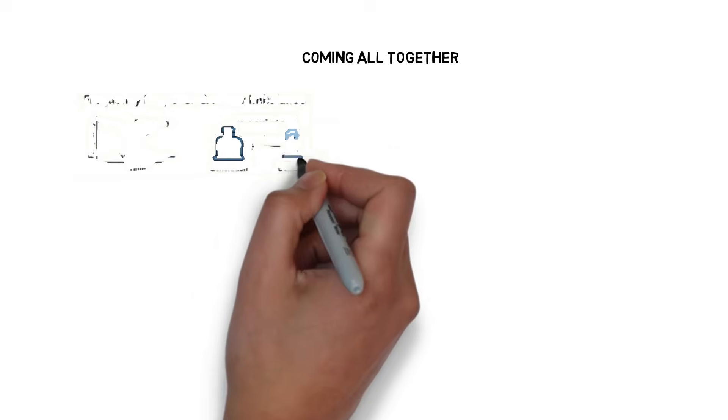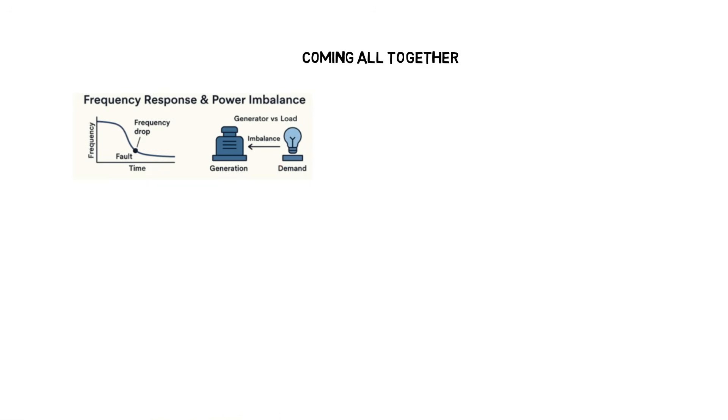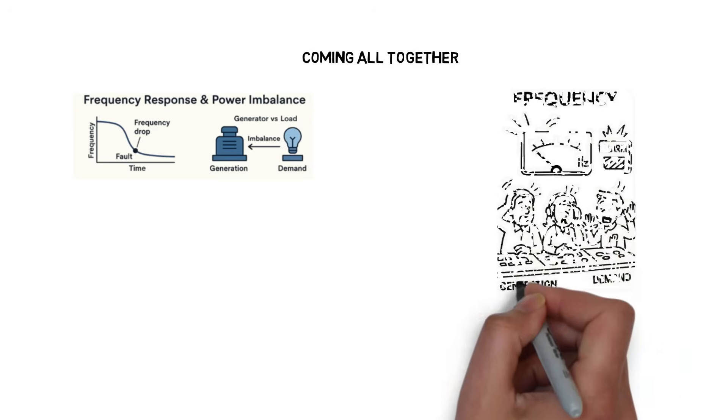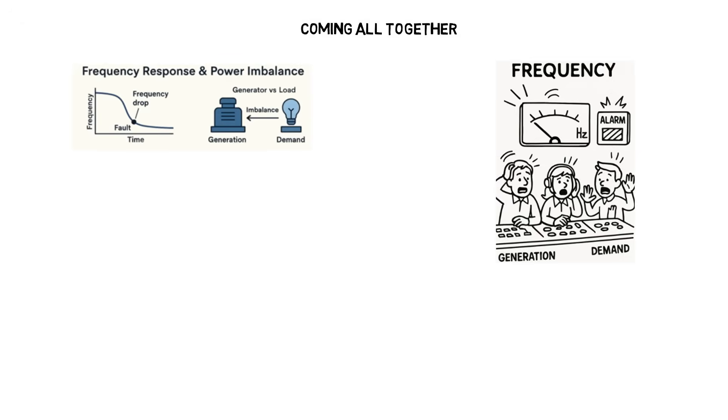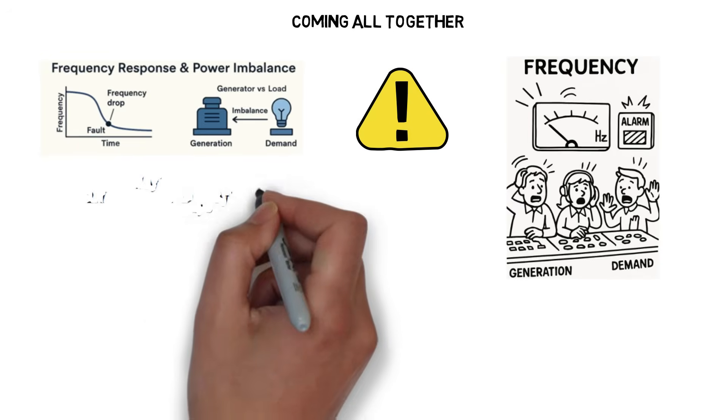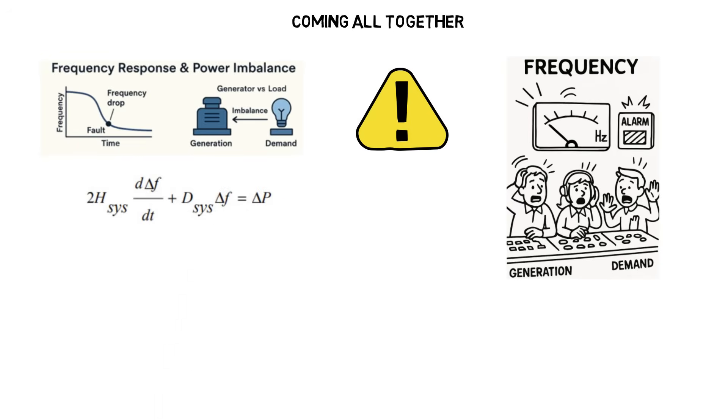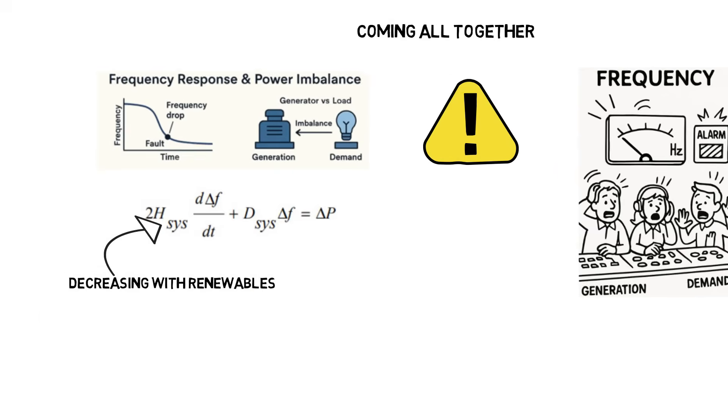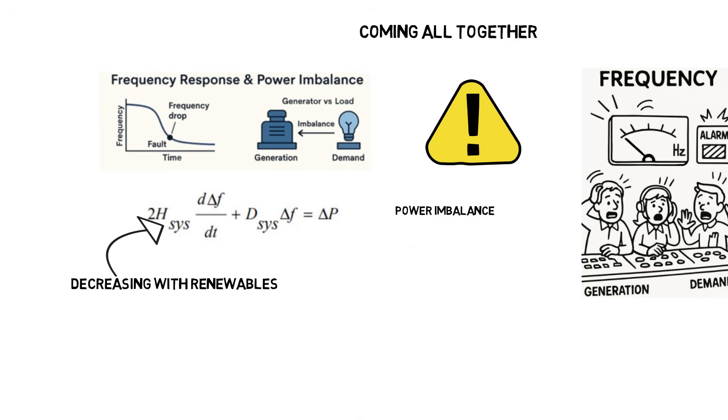When electricity generation perfectly matches demand, the frequency holds steady, locked at 50 hertz. But when that balance is disturbed, say demand spikes suddenly, or a fault hits the system, the frequency begins to shift. This dynamic is captured by the swing equation. Two times the system inertia, multiplied by the rate of frequency change, plus the damping effect, equals the power imbalance.